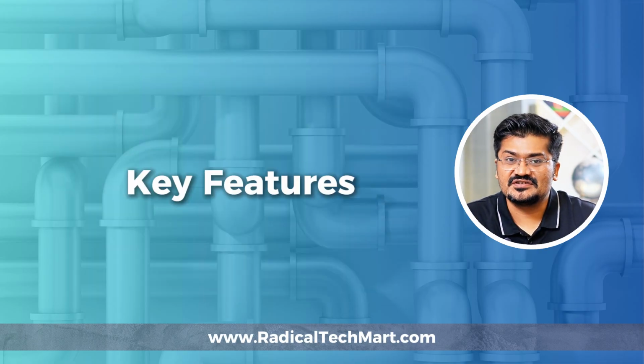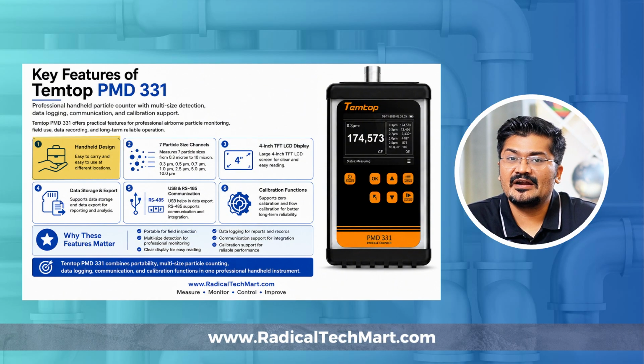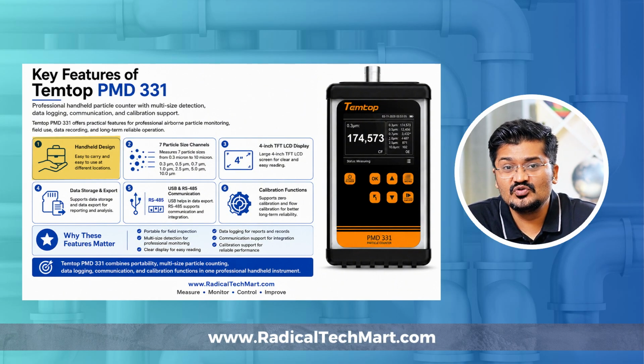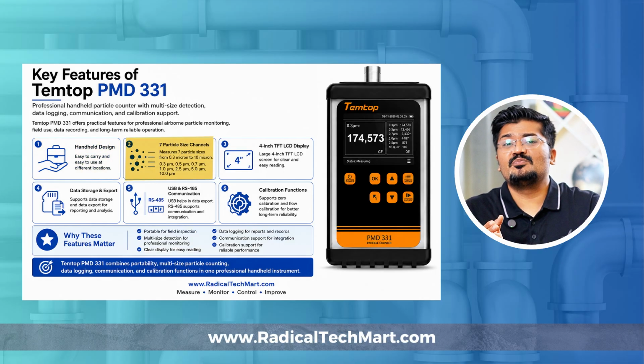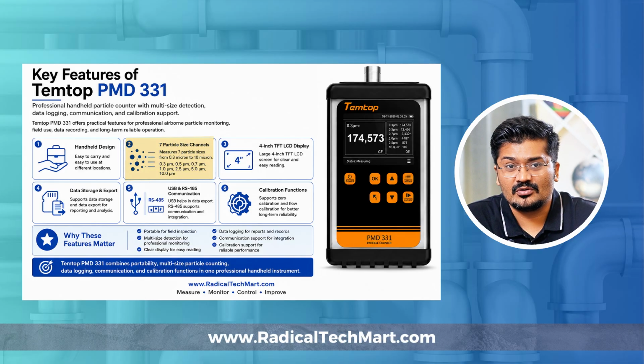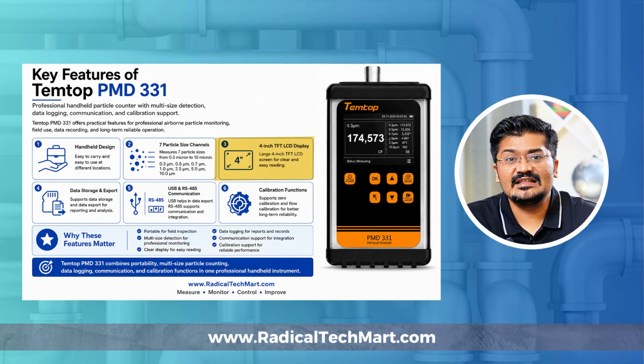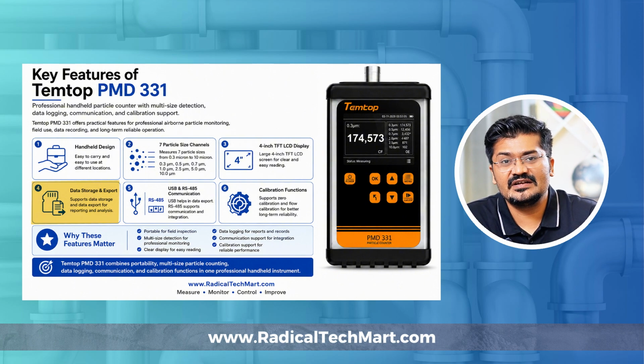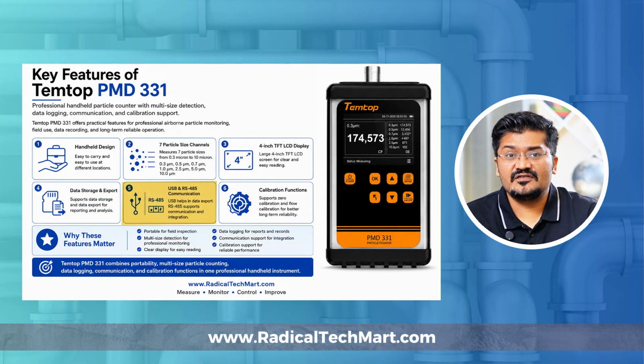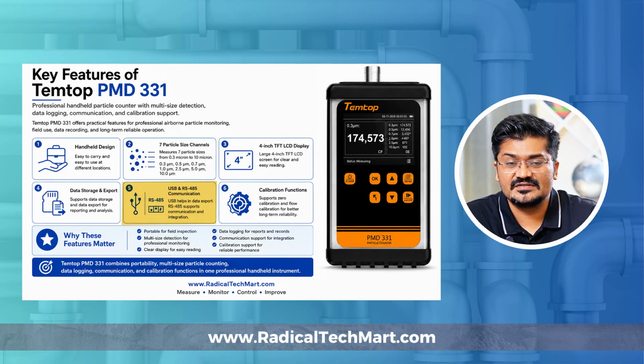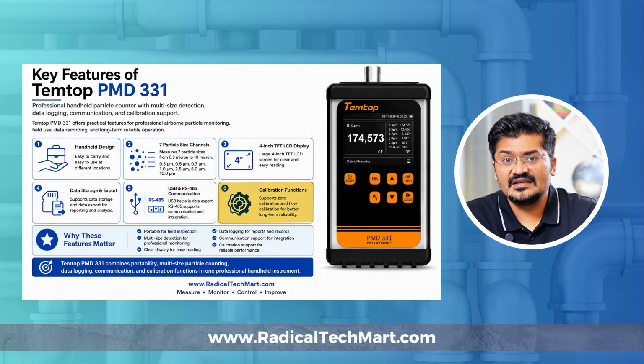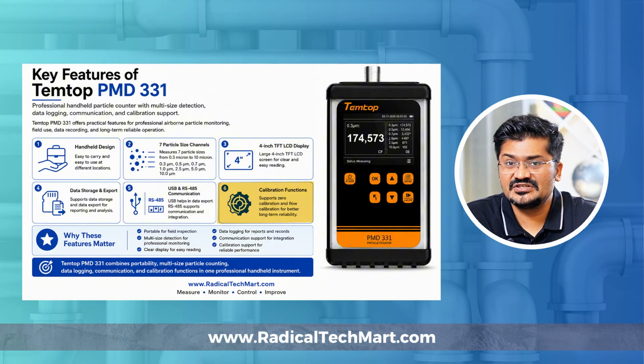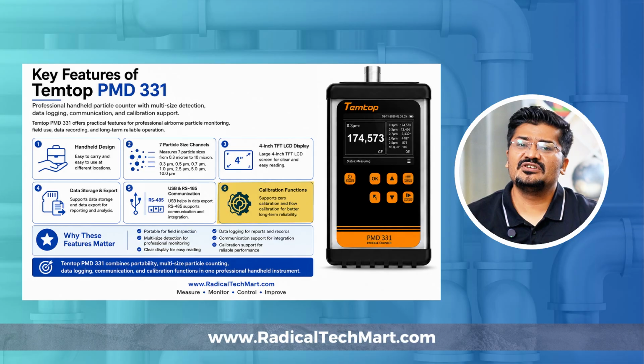Now let's talk about the key features. The first feature is that it is a handheld particle counter. So it is easy to carry and easy to use at different locations. Second, it measures 7 particle sizes from 0.3 micron to 10 micron. Third, it has a 4-inch TFT LCD display, so the readings are easy to see. And the fourth, it supports data storage and data export also. So users can save readings and use the data later for reporting or analysis. Fifth, it has USB and RS485 communication options. USB is useful for data export. RS485 can be useful for communication and integration. And sixth, it supports calibration related functions like zero calibration and flow calibration. This helps to maintain better reliability during long-term use.